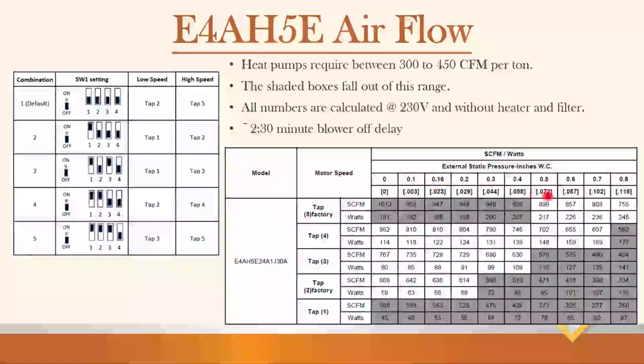So what you're going to want to do is take your static pressure. We go up to 0.8 inch. White, we want to be in the white right here. So tap 2 is factory. Tap 5, high speed. So low speed, high speed. Excuse me. No, this is high speed, right? So tap 4 at 0.5 inches static.